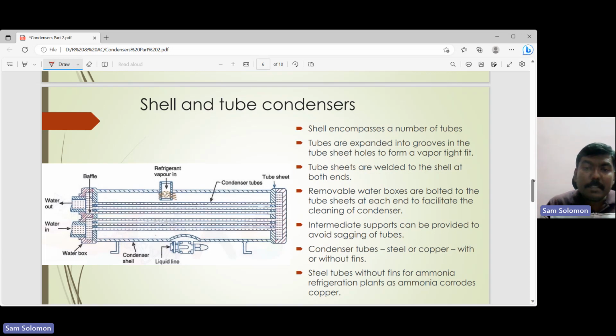You can see this is a tube sheet over here, and the tubes are connected to the tube sheet. You can see the holes in the tube sheet where your tubes can be fixed or welded together. Okay, and you can also see water boxes over here, through which water enters and leaves. So this is actually a double pass condenser. So you have water entering through this, and then you have the water going out through this.